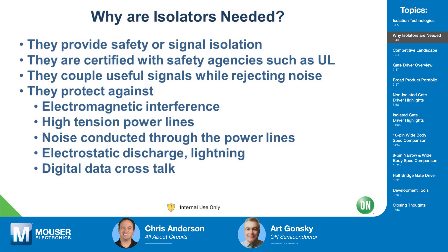The number one reason for isolation is to provide safety and signal isolation simultaneously, and these products are certified with safety agencies such as UL. Isolation is also very useful to reject noise from input to output, and it protects against magnetic interference, electromagnetic interference, high-tension power line noise conducted through power lines, electrostatic discharge, lightning, and digital data crosstalk.